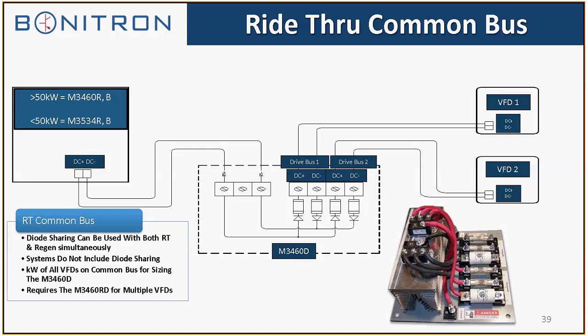This is a 2-drive common bus. As you can see, positive and negative connections from the VFD to the diode module, and the diodes connect over to the DC plus and negative of the ride-through unit. You size the M3460D to each leg, which has to handle the current from one drive. We have a full module rating which takes into consideration the total drives, but the important part is making sure that you size the diode module to handle the maximum current per leg.